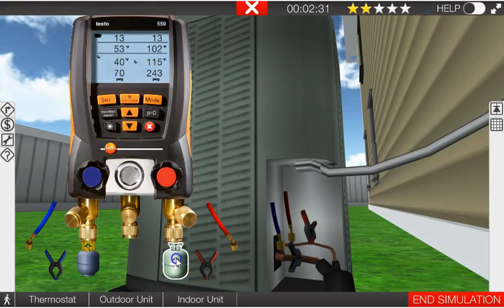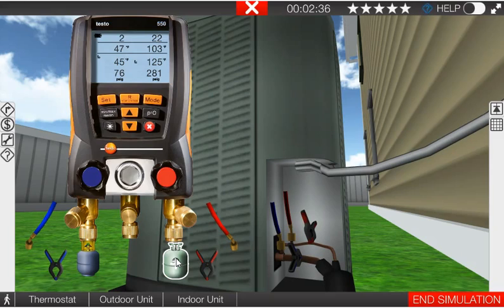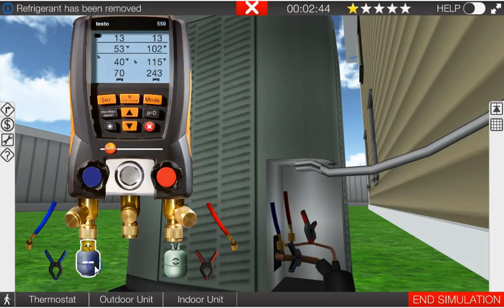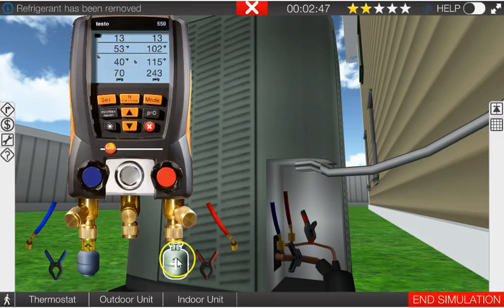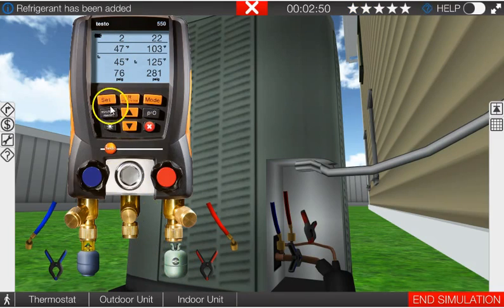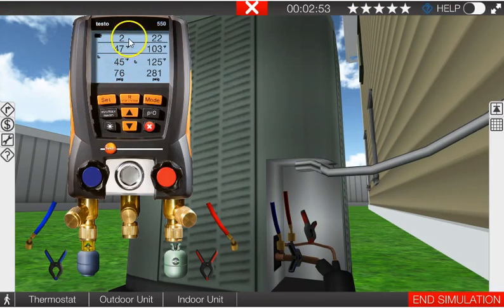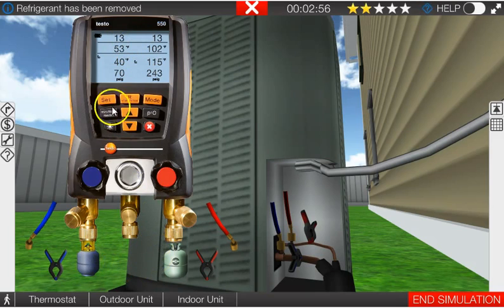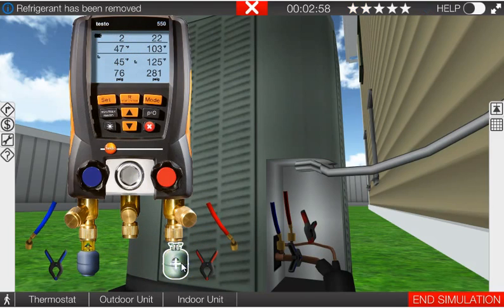Let's add a little refrigerant. Now this isn't going to happen immediately, but on a real system it's going to take five or ten minutes for these pressures to stabilize. But look what happened: we went from 13 degrees of superheat, if we overcharge the system superheat decreases down to two degrees. You see that? We go from 13 to 2.